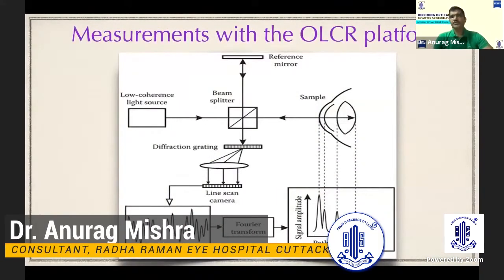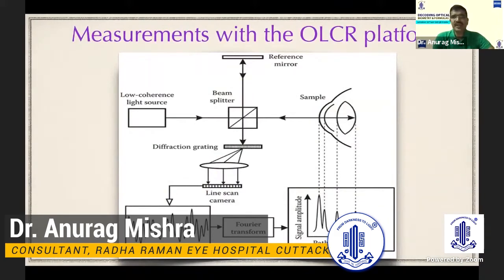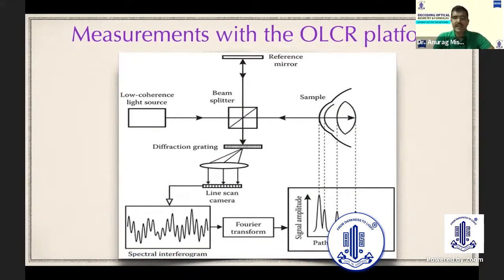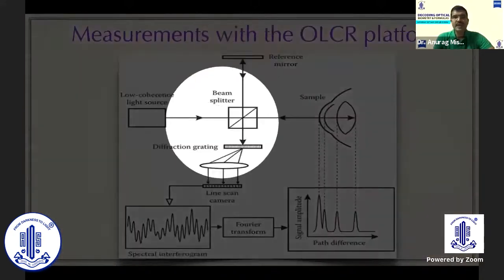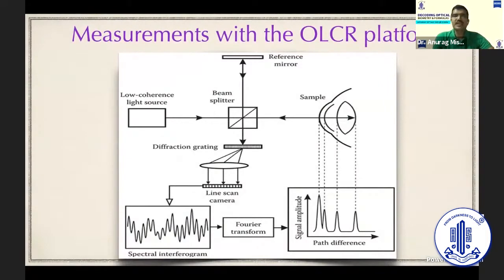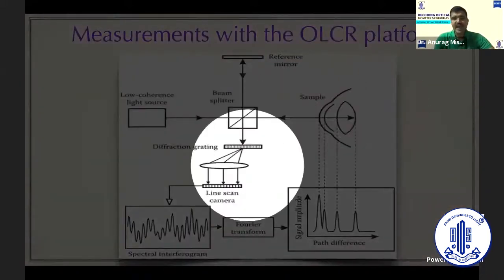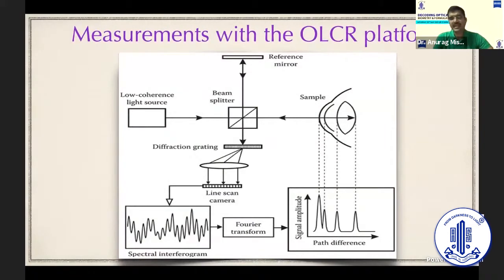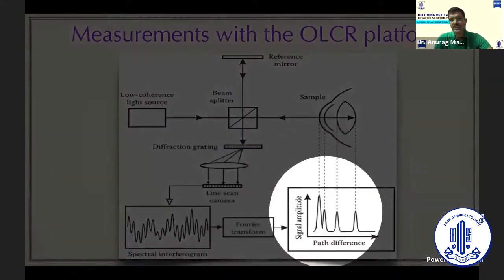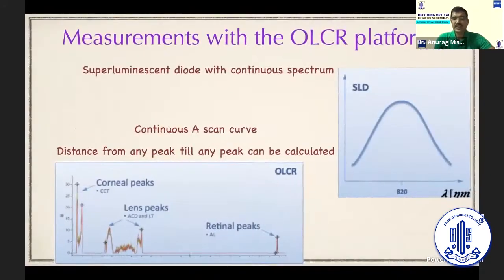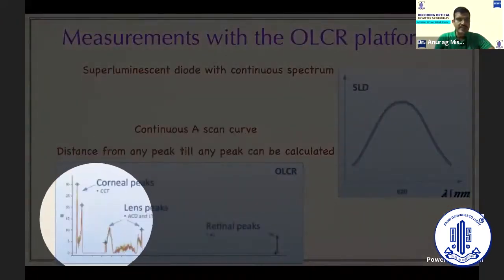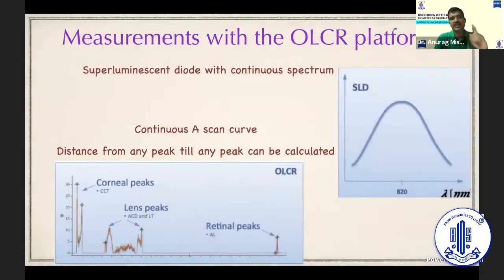So to correct that, the next platform came in, which was optical low-coherence reflectometry utilized by LENSTAR LS900. We had only one reference mirror instead of two. The light source was a super-luminescent diode which had a single peak. The wavelength improved to 820 nanometers, which improved the penetration. It also had waveforms coming from the subject's eye, which were matched with a reference wave, which was incorporated into the database of the machine. Both of the waves underwent Fourier transformation to give us a single A-scan curve. Now, the advantage of the single A-scan curve is we can determine the distance between any two peaks, and which can give us things like the pachymetry, the anterior chamber depth, and the lens thickness.